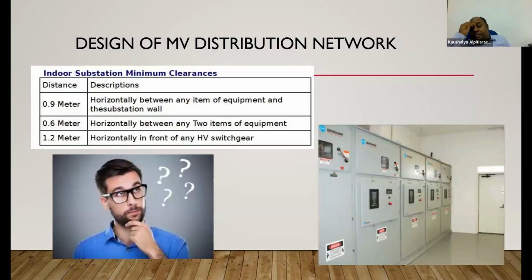Yes, is that actually enough? Distances, indoor substation minimum clearances: 0.9 meters horizontally between any item of equipment and the substation wall, 0.6 meters horizontally between any two items of equipment, 1.2 meters horizontally in front of any HV switchgear. Is it really enough?